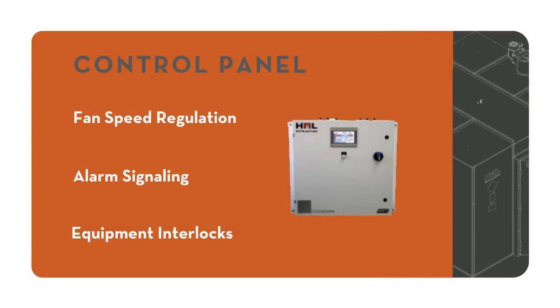And with that, a lot of jurisdictions will require that you have those shut off when you get to maybe that 25% threshold. It is dependent on your jurisdiction. Some might be stricter and require it at a lower threshold. Some might require it only when your fire suppression goes off. But you can interlock any components into our control panel. So if some condition is met within the room, it shuts off that equipment. And then the last interlock is a fire panel interlock.